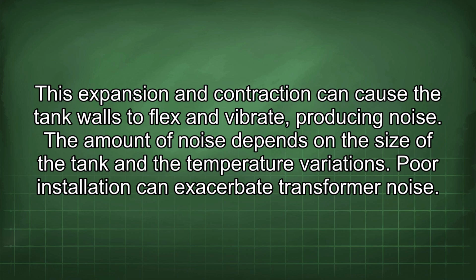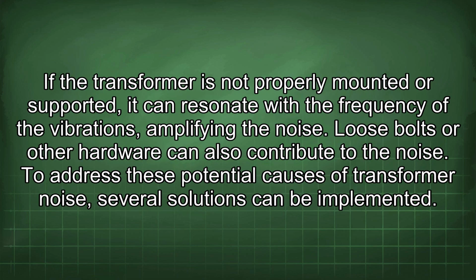Poor installation can exacerbate transformer noise. If the transformer is not properly mounted or supported, it can resonate with the frequency of the vibrations, amplifying the noise. Loose bolts or other hardware can also contribute to the noise. To address these potential causes of transformer noise, several solutions can be implemented.